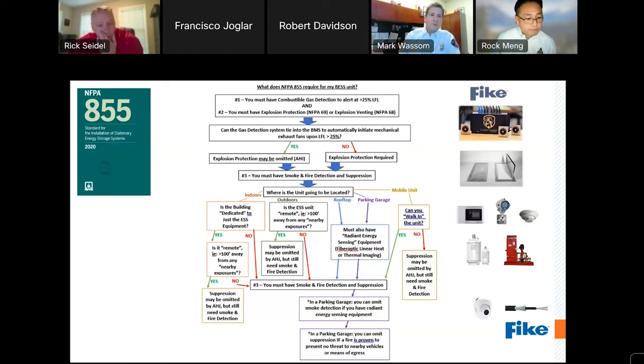From there are many yes/no type questions, and the AHJ's interpretation and requirements come into play based on where the unit is going to be located, generally classifying the energy storage system as being either indoors, outdoors, on a rooftop, in a parking garage, or being a mobile unit. These are some of the key indicators, along with whether it's remote or nearby to other areas, that will drive you to ultimately what the codes will provide as guidance for the best level of protection for your unit. But they can, again, always be combined or integrated with one another to provide even higher levels of detection.